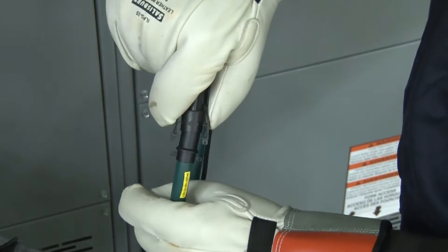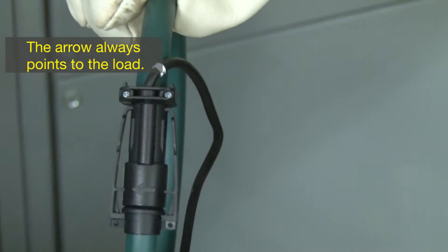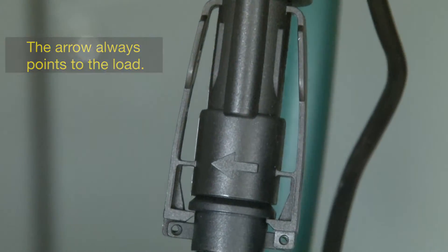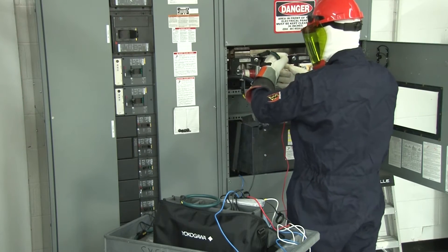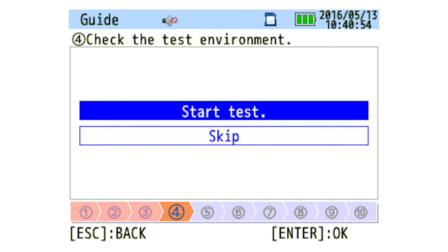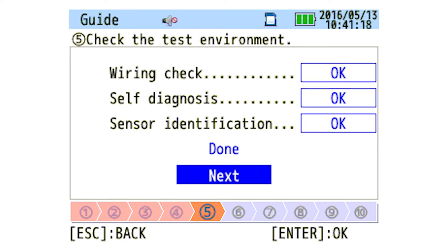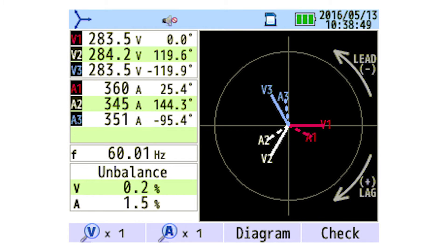Simply give the CW500 a target power factor and it will calculate capacitance for you. The CW500 is very user friendly and easy to operate. With the use of the quick start guide, the CW500 will walk you through your setup step by step to assure all of your settings and connections are correct. Wiring diagrams are displayed based on wiring configuration selected. Vector diagrams are also displayed.